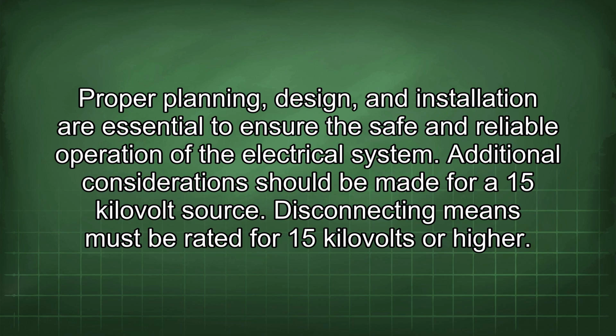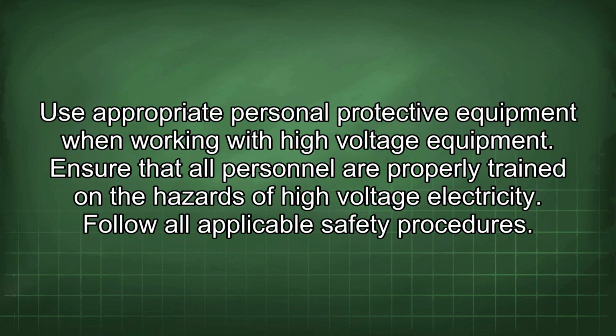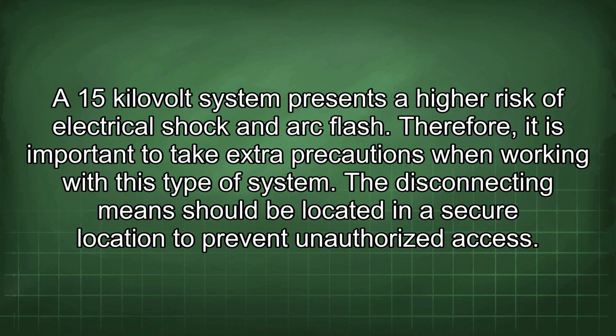Additional consideration should be made for a 15 kV source. Disconnecting means must be rated for 15 kV or higher. Use appropriate personal protective equipment when working with high voltage equipment. Ensure that all personnel are properly trained on the hazards of high voltage electricity. Follow all applicable safety procedures. A 15 kV system presents a higher risk of electrical shock and arc flash. Therefore, it is important to take extra precautions when working with this type of system.